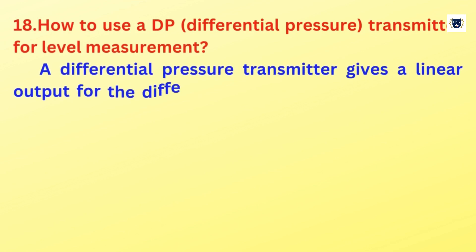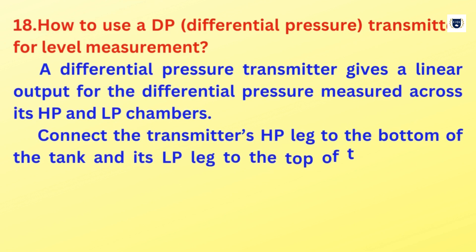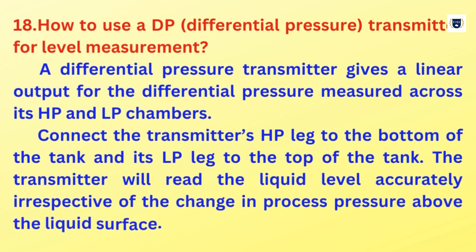How to use a DP (Differential Pressure) transmitter for level measurement? A differential pressure transmitter gives a linear output for the differential pressure measured across its HP and LP chambers. Connect the transmitter's HP leg to the bottom of the tank and its LP leg to the top of the tank. The transmitter will read the liquid level accurately irrespective of the change in process pressure above the liquid surface.